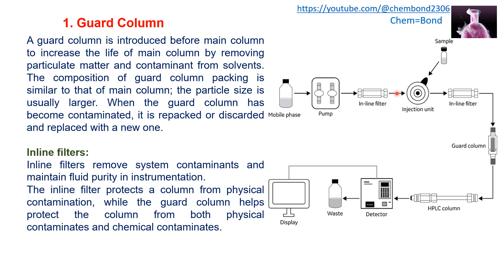The inline filter removes dust particles or any particulate material moving toward the main column — it filters out physical contaminants only. The guard column traps both physical contaminants (particulates) and chemical contaminants that would react irreversibly with the packing material of the main column. So the inline filter handles physical contaminants, while the guard column handles both physical and chemical contaminants.